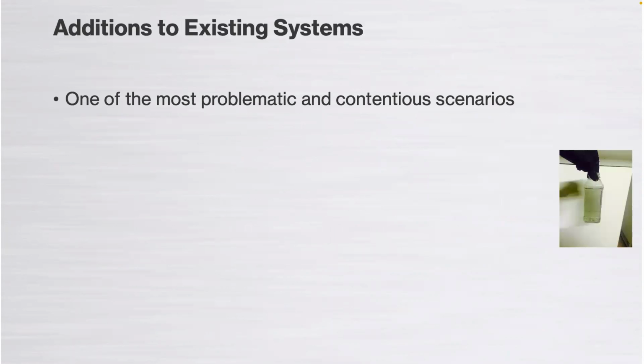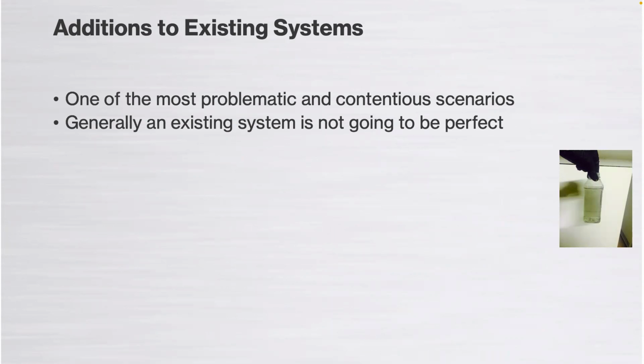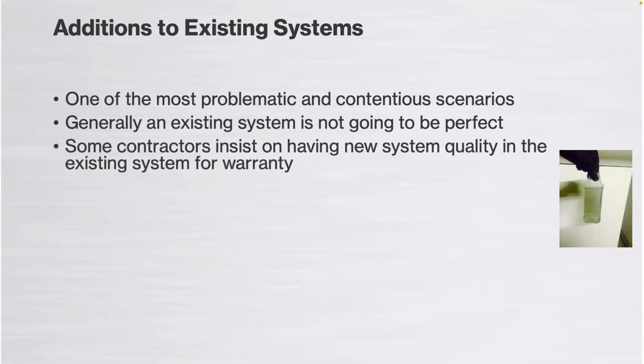I mentioned existing systems. It's really one of the most problematic and contentious scenarios. Generally, you're never going to have an existing system in good condition; it's not going to be perfect. And yet you're adding new plant and equipment to it. So you just need to be mindful of that. Some contractors may insist on having new system water quality in an existing system from a warranty point of view. Well, how do you do that if you've got a very old, 20-year-old system, new boilers going in, no plate heat exchanger, no hydraulic separation? How do you manage that? How can you offer that level of warranty? It becomes challenging. And I think it's about managing expectations from the get-go, really. It's normally impossible to achieve.